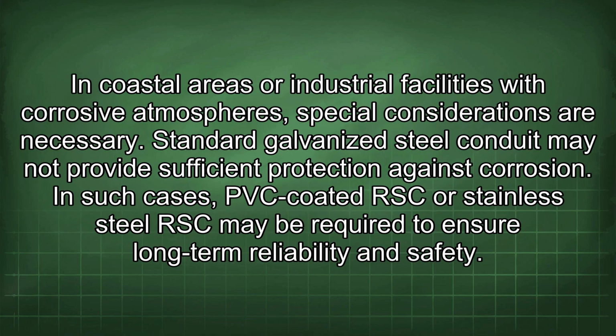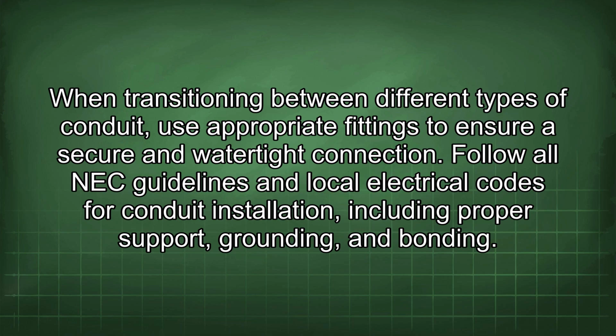In coastal areas or industrial facilities with corrosive atmospheres, special considerations are necessary. Standard galvanized steel conduit may not provide sufficient protection against corrosion. In such cases, PVC-coated RSC or stainless steel RSC may be required to ensure long-term reliability and safety. When transitioning between different types of conduit, use appropriate fittings to ensure a secure and watertight connection. Follow all NEC guidelines and local electrical codes for conduit installation, including proper support, grounding, and bonding.